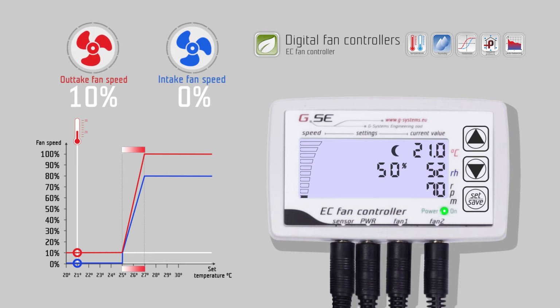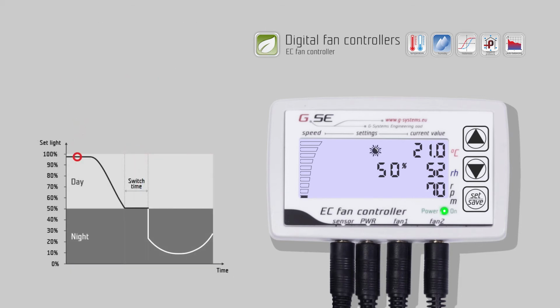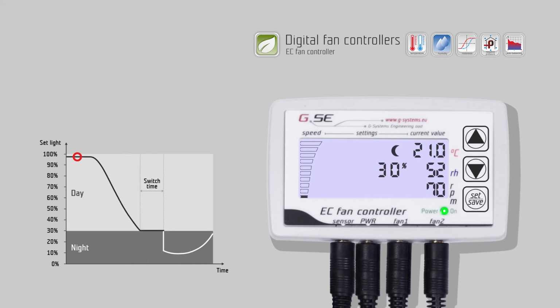Press down to go to the light sensor switch setting. You can see the alternate blinking of the sun and moon segments. Press Set Save to change the switch level value between day and night time. If the value is set to 30% light, then the controller will switch settings when the light is below 30%.